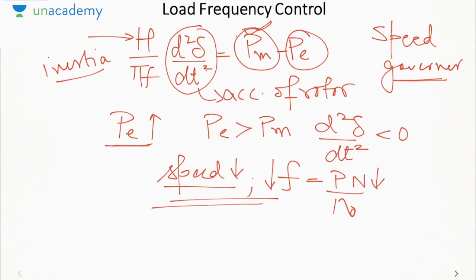So that is the secondary method. So this speed governor is the primary method of frequency control. Secondary method is by controlling the real power output of a machine. So voltage is controlled by controlling the reactive power output of a machine, and frequency is controlled by controlling the real power output of a machine. Now let us see this secondary method, how we can shed the load or how we can share the load between different machines to control the frequency.